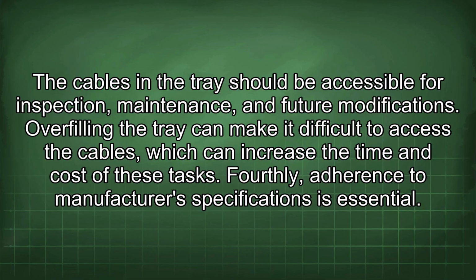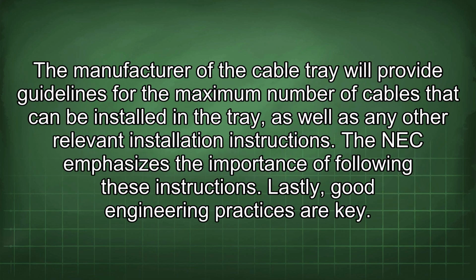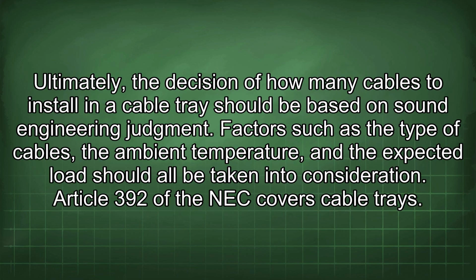Fourthly, adherence to manufacturer's specifications is essential. The manufacturer of the cable tray will provide guidelines for the maximum number of cables that can be installed in the tray, as well as any other relevant installation instructions. The NEC emphasizes the importance of following these instructions. Lastly, good engineering practices are key. Ultimately, the decision of how many cables to install in a cable tray should be based on sound engineering judgment. Factors such as the type of cables, the ambient temperature, and the expected load should all be taken into consideration.